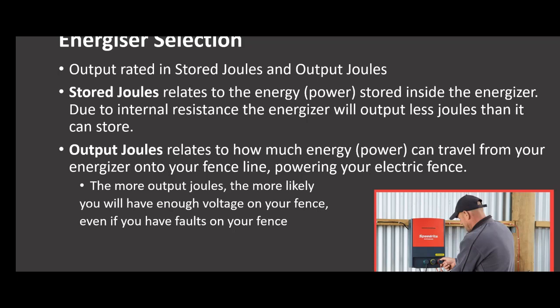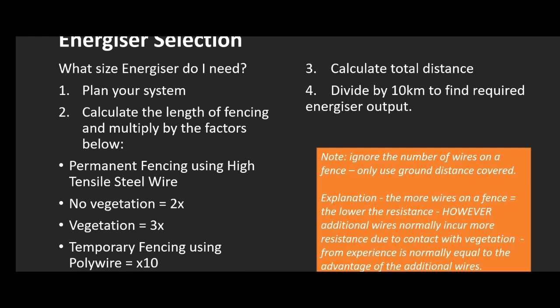When selecting an Energizer and answering the question of what size you need, it's worth planning your system, calculating the length of fencing, and multiplying by certain factors. Most Energizers will tell you on the box that 1 joule is sufficient for 10 kilometers of fencing. That might be true in theory, but it's never true in practice. So we'll talk you through a process to work out the actual power requirement for your system, accounting for things like vegetation and polywire, which has much higher resistance due to its thinner metal filaments, meaning the Energizer won't power as large a distance of it.